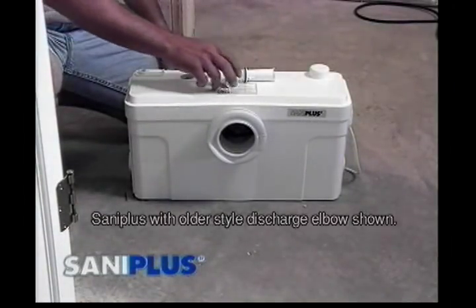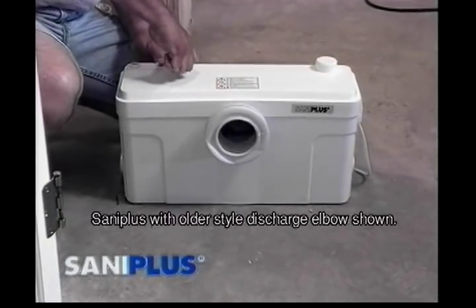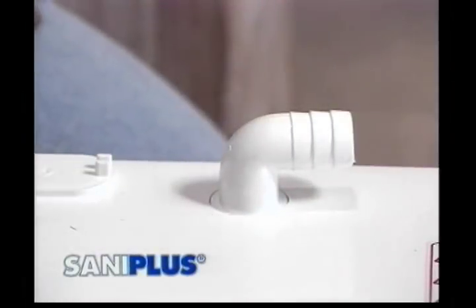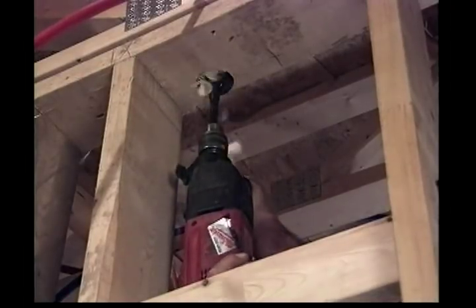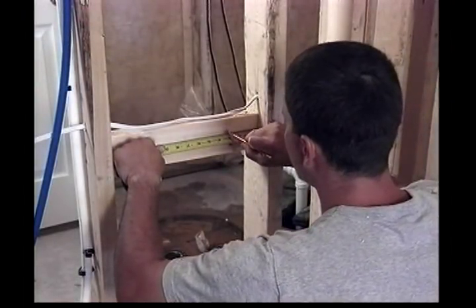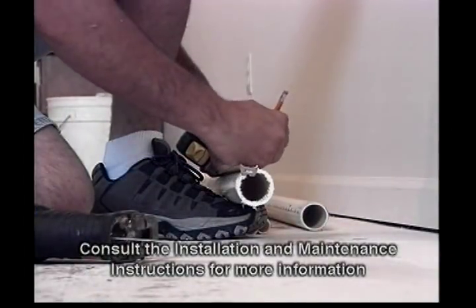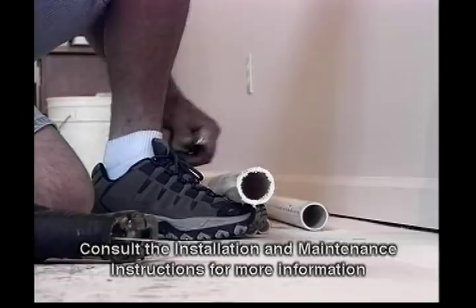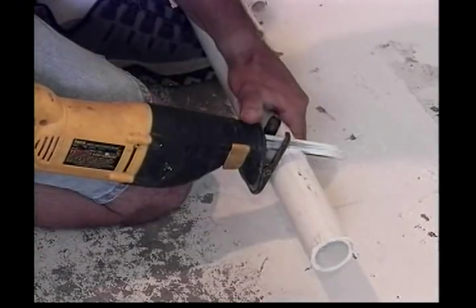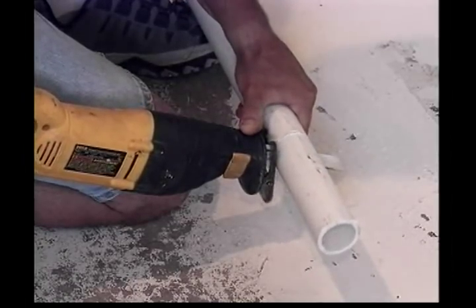The first step in installation is to prepare the macerating pump unit. For Saniplus systems, install the discharge elbow into the round opening in the lid, then press down and twist the elbow at the same time. The macerating system will pump a maximum of 12 feet vertically or 150 feet horizontally with a 1/4 inch per foot gravity fall to the point of discharge. For every three feet of vertical distance the discharge pipe travels, it's necessary to subtract 30 feet of horizontal distance from the maximum. If a vertical lift is required, it should come before any horizontal run to allow for efficient pumping.